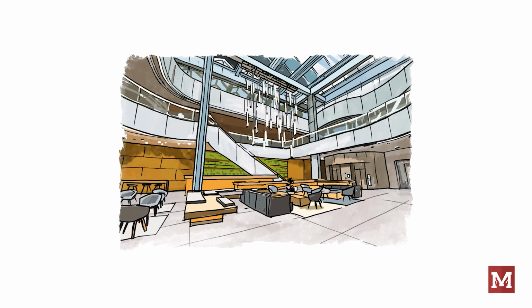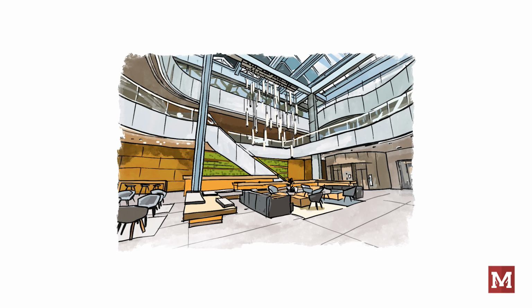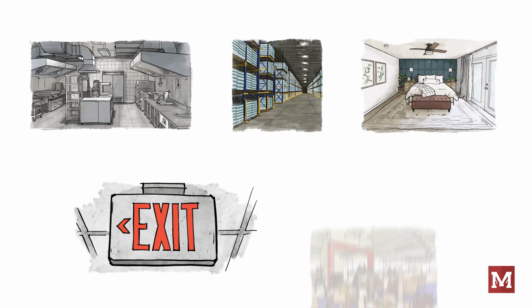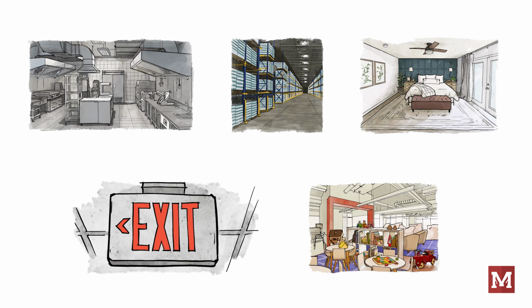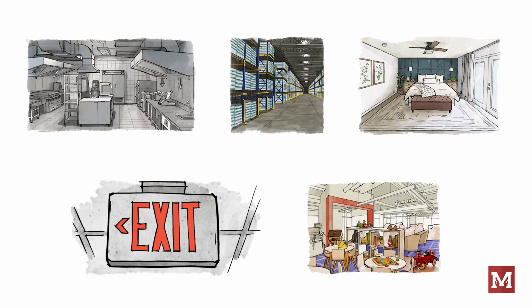In an ideal world, we would have open and clear rooms void of anything that blocks a fire alarm appliance. But in the world we occupy, unfortunately, we've got decorations, wall art, curtains, furniture, and then more practical things too, like kitchen service equipment, storage racks, ceiling fans, exit signs, cabinets, plenty of other things that can block light. The rule is that we need to achieve the light intensity on floor spaces throughout each area that needs visual coverage. Practically speaking, let's say we have a column that partially blocks direct coverage from a wall-mounted strobe.